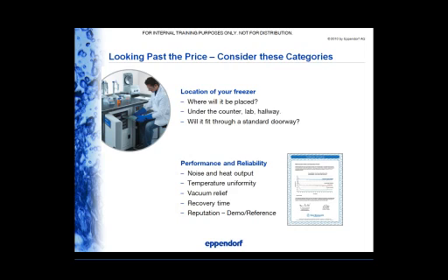Ask about vacuum release provisions. If it's a freezer that is accessed multiple times during the day, you'll need some type of vacuum release method. I'm sure everyone has experienced the vacuum effect of ultra-low freezers, and that's where the outer door cannot be reopened right after closing it. So some freezers actually have devices that safely relieve vacuum, so you don't have to take a screwdriver to the gasket and risk damaging it.